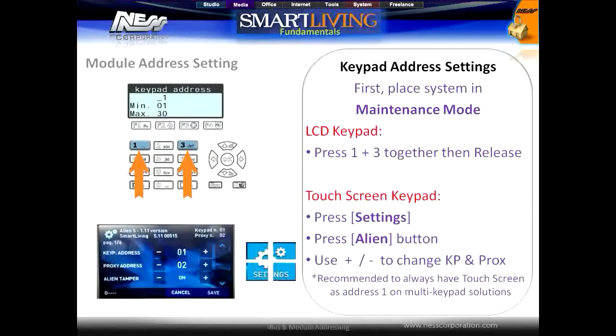Programming keypad addresses is done by placing the system first into maintenance mode. For the LCD keypad, press the 1 and 3 buttons together and then release, and use the up and down arrows to change the keypad address. For touchscreens, press the settings button followed by the Alien button, and you will find the keypad address and the prox reader address setting at the top of the list.